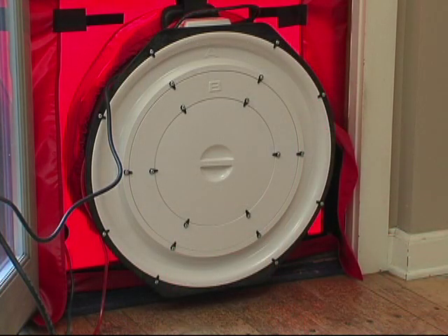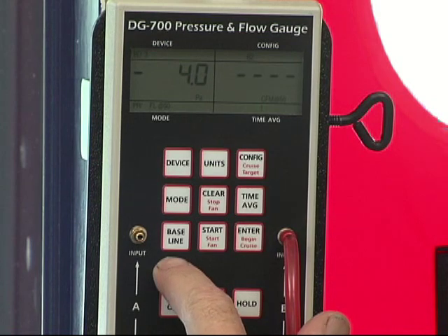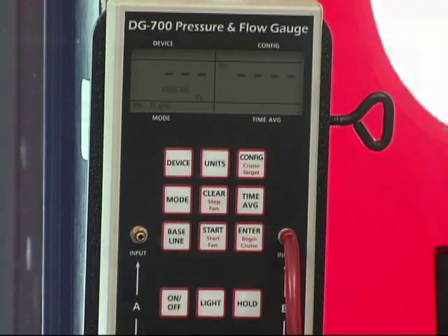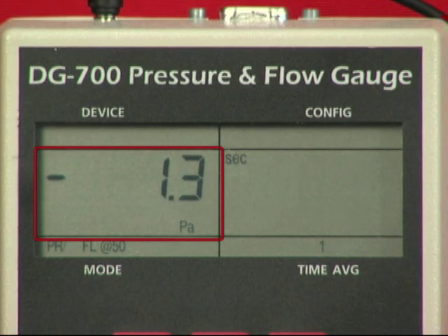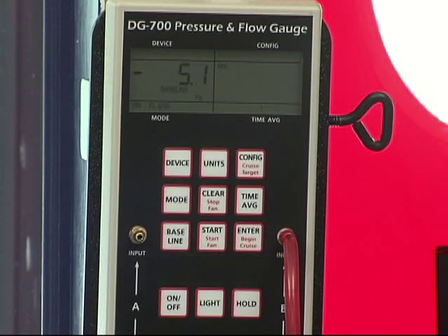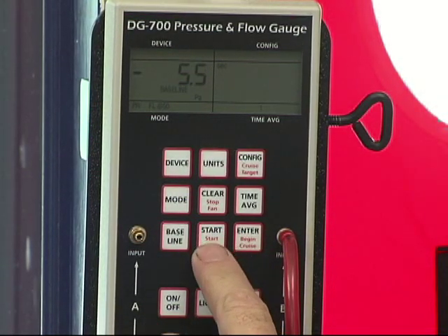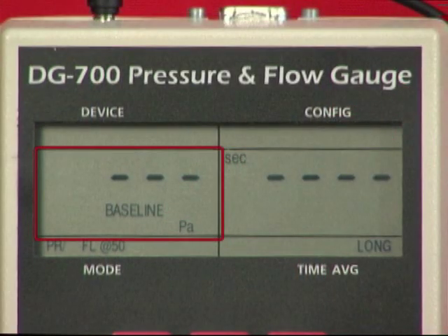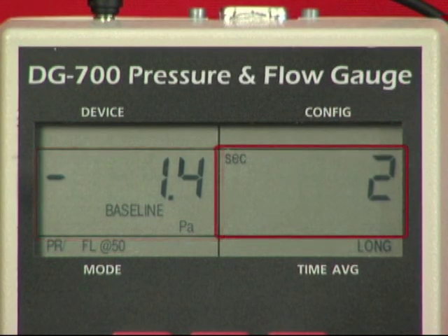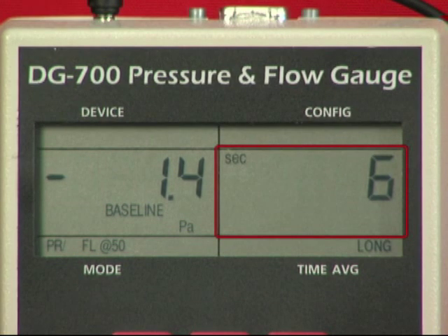With the fan sealed off, begin a baseline building pressure reading from channel A by pressing the baseline button. The word baseline will begin to flash in the channel A display, indicating that the baseline feature has been initiated. Press Start to start the baseline measurement. During a baseline measurement, channel A will display a long-term average baseline pressure reading while channel B is used as a timer in seconds to show the elapsed measurement time.